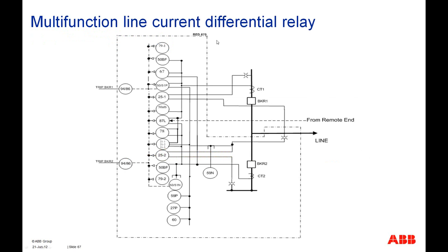RED 670, as we said, is the line differential relay from ABB, a numerical relay, and it has these protection functions, which you can see. It not only includes the line differential protection, but also a backup distance protection, in addition to breaker failure and all other protection functions.